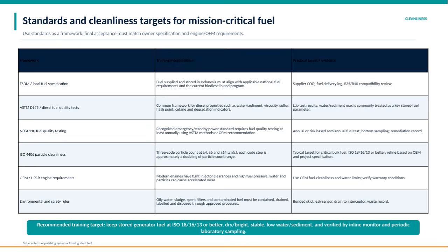ISO 4406 addresses particle cleanliness through a coding system that counts particles at different sizes. For mission-critical systems, a typical target is ISO 18/16/13 or better, but this should be refined based on manufacturer and project-specific requirements. OEM and high-pressure common rail engine requirements are stringent because modern engines have very tight injector clearances and operate at high fuel pressures, making them highly sensitive to water and particle contamination. Following OEM limits ensures engine longevity and warranty compliance.